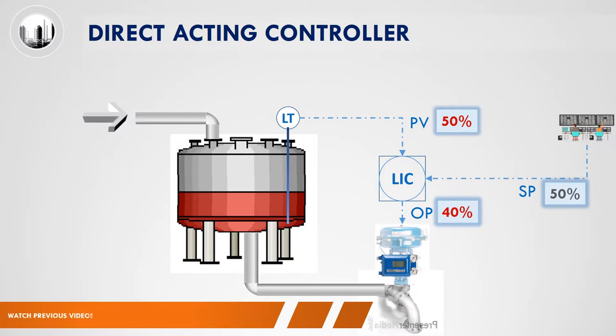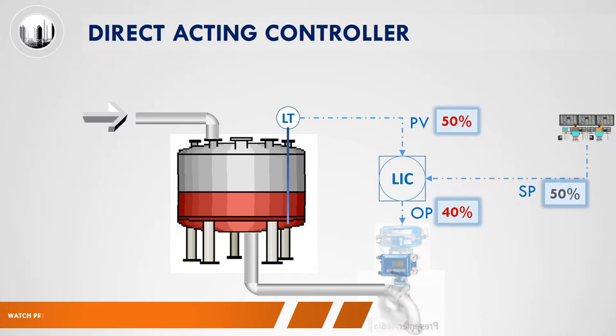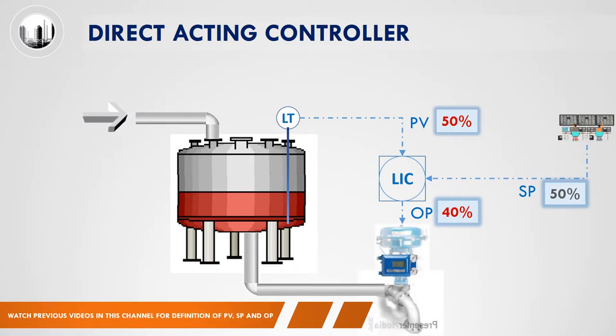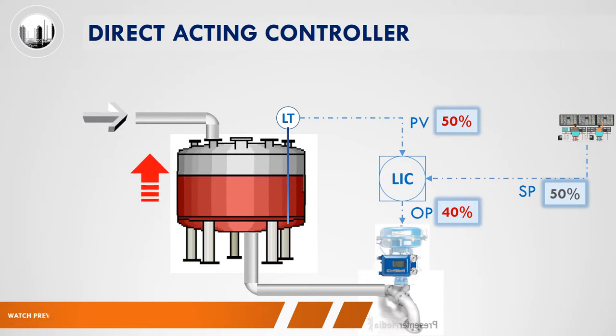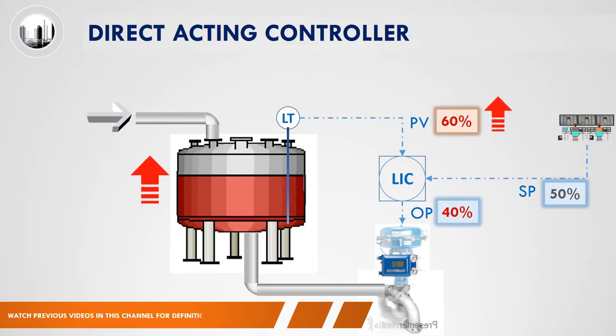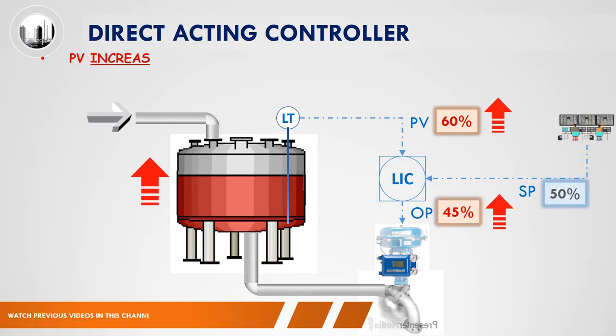This diagram shows an example of a direct acting controller. As shown in this diagram, the control valve is located at the outlet of the tank. In this example, we will evaluate the scenario when the level in the tank increases. The increase of the tank level will be measured by the level transmitter. When the tank level increases, the control valve at the outlet of the tank will open more to allow the liquid to be drained faster.